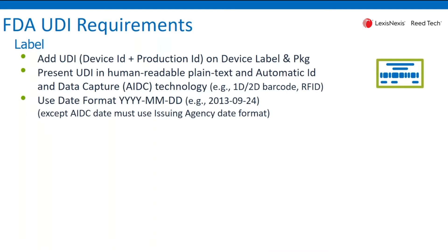Basically, the information that needs to be included on the label has to be expressed — the UDI information has to be expressed in human-readable plain text and also in something called automatic ID data capture, AIDC, so that is usually implemented as a one-dimensional or two-dimensional barcode.